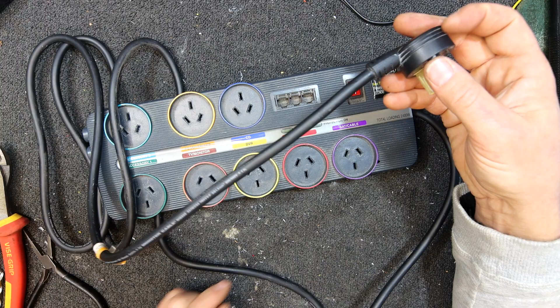1.5mm square, so bigger than usual, but the circuit breaker will cut out at 10 amps. Your power point's not rated for more than 10 amps, so if it's got like a 15 amp cord on it, it's just big and thick and a pain, and you're paying for extra copper you don't need and will never use. So no point in that at all - just another monster cable gimmick.